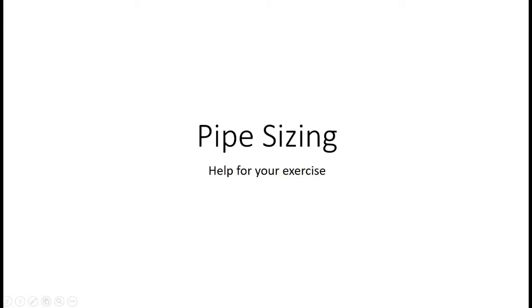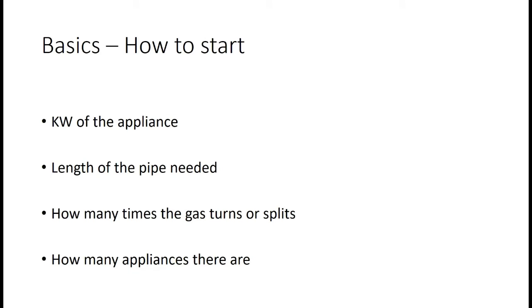Pipe sizing: the basics. In order to pipe size, you need to know four basic elements of the installation. You need to know the kilowatts of the appliance, the length of the pipes that are needed, how many times the gas turns or splits, and how many appliances there are in the installation.